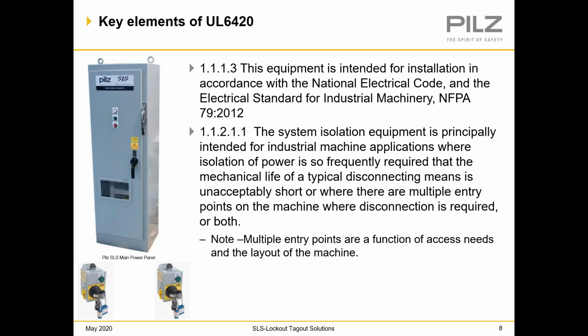The system isolation equipment is principally intended for industrial machine applications where isolation of power is so frequently required that the mechanical life of a typical disconnect means is unacceptably short, or where there are many entry points on the machine where disconnection is required, or both. Multiple entry points are a function of the access needs and the layout of the machine itself.